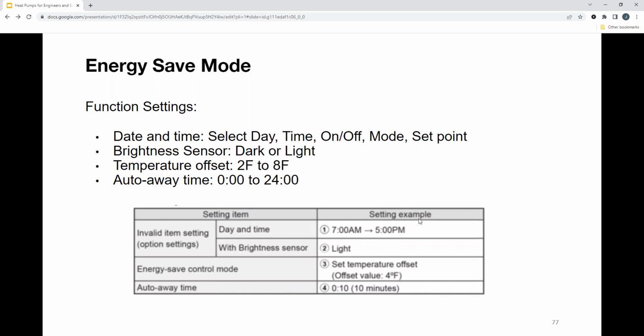But also, if you don't want to set that up, you are able to go through the central controller and set up block sweeps, which means you can group a certain amount of fan coil units on the floor, set that into a block, and then every hour sweep the floor and make sure that your temperature and mode are exactly where you want them to be. Because in a heat pump system, and I haven't mentioned this yet, it's always last command wins. So if I adjust something on the BMS, it funnels down, and that's what the command is going to be. But as soon as an occupant goes to a local thermostat and adjusts whatever they want, then that command is going to win. So it's always last command wins when we're talking about control.